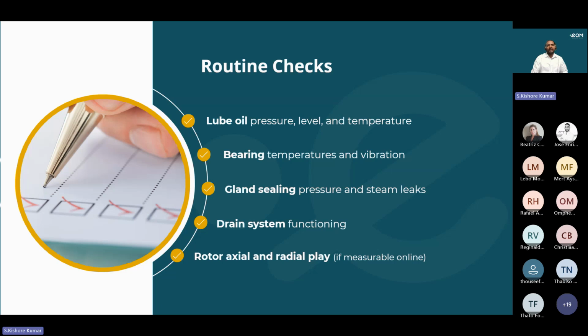So daily and shift-wise checks include lube oil pressure, lube oil level, and lube oil temperature, bearing temperatures, vibrations, gland sealing pressures, steam leaks, drain system functioning, and also rotor axial and radial play, if we are able to measure.